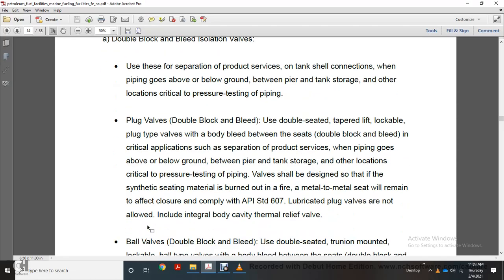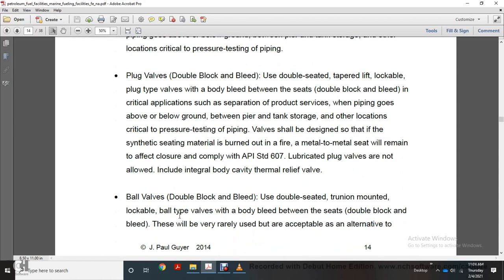Plug valves: use double block and bleed, double seated, with a tapered lift, lockable plug type valve with a body bleed between the seats of the double block and bleed in critical applications such as separation and product services, when piping goes above and below ground between pier, tank storage, or other locations critical to pressure testing of pipe. Valves will be designed so that if the synthetic seat material is burned out in a fire. Metal to metal seats will remain to effect closure. Comply with API standard 607. Lubricated plug valves are not allowed. Include an integral body cavity thermal relief valve.